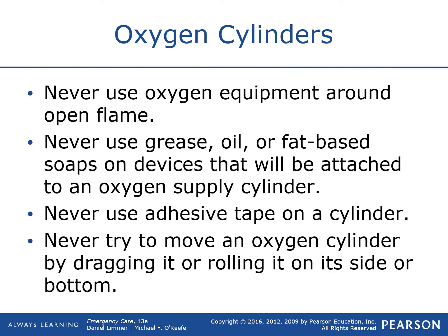So it says never use oxygen around an open flame. Never use grease, oil, or fat-based soaps on devices that will be attached to an oxygen supply cylinder. Don't use adhesive tape on a cylinder, and don't try to move an oxygen cylinder by dragging it or rolling it on the side. Some pretty common sense. Just treat an oxygen cylinder carefully. Don't be doing anything stupid with it.